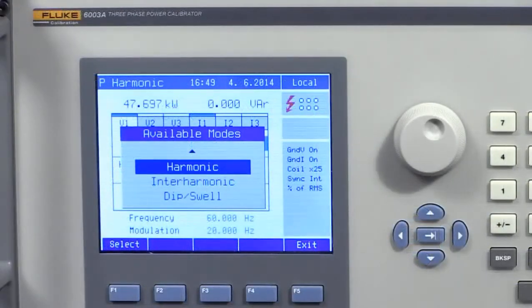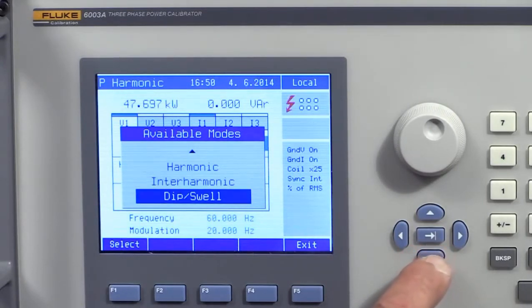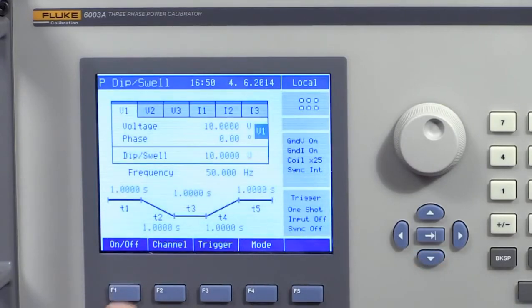The power quality option enables the 6003A to calibrate power quality instruments by generating up to 63 harmonics, an interharmonic, modulation or flicker, and dips and swells on any or all of the three phases of current and voltage.